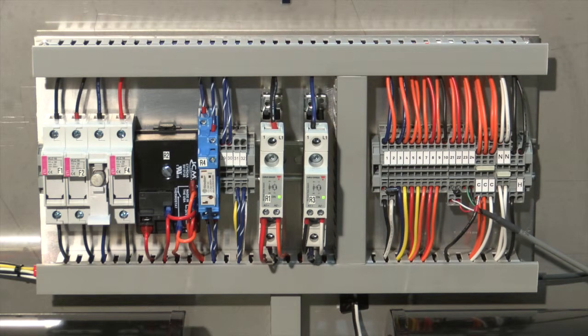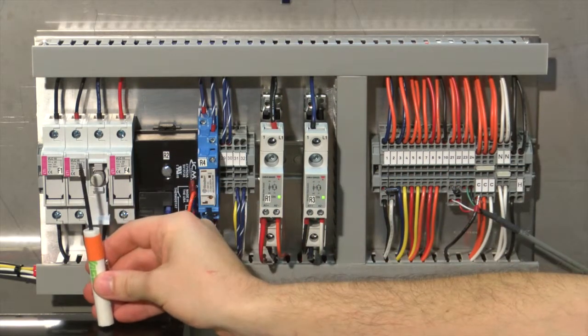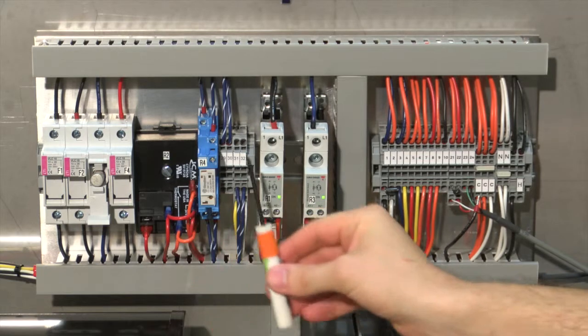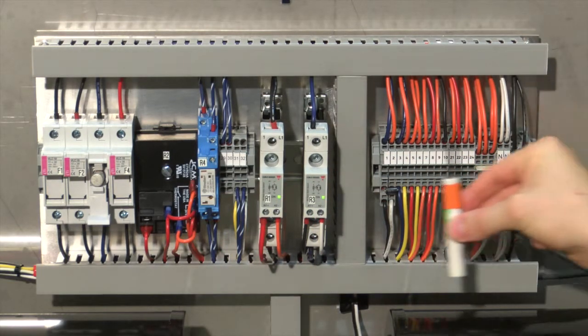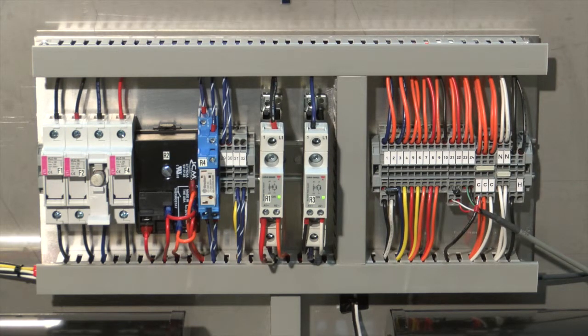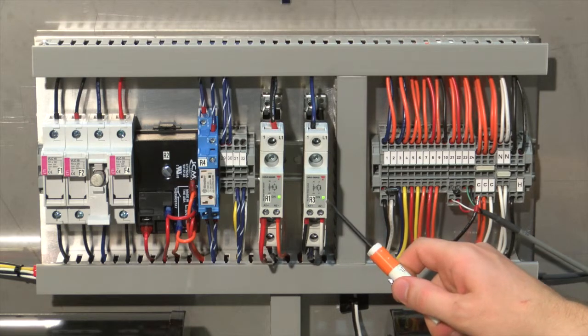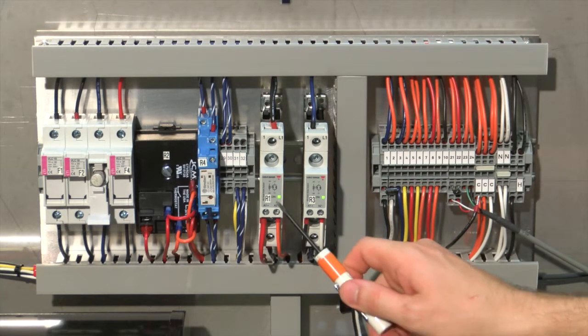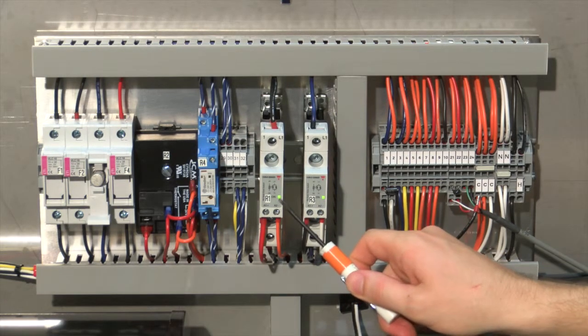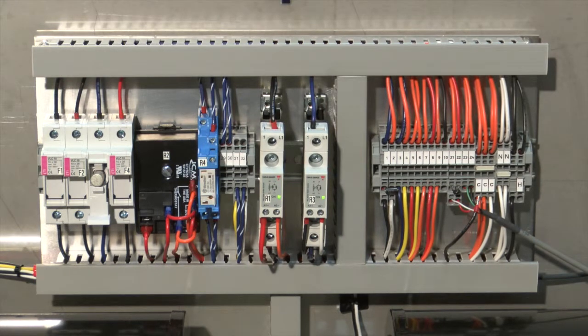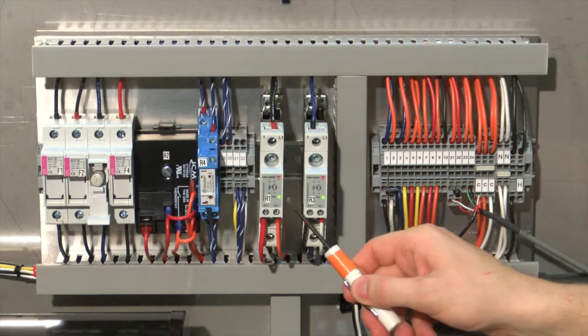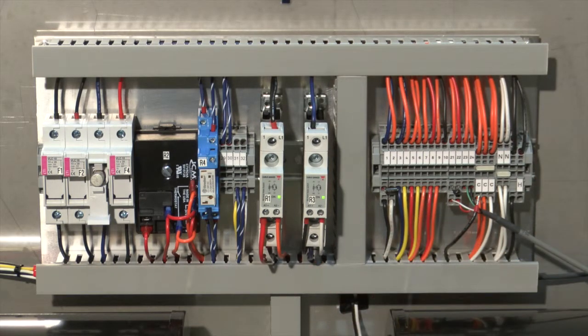A failed or damaged component will also not allow your system to operate correctly. Looking at the mist freeze interface plate, you will see the fuse block, the R2 relay, the R4, the R1, the R3, and the terminal block to connect the wiring. The transducers are controlled by the R1 and R3 solid-state relay. When the transducers are operating, both these relays should be lit green. If your transducers are not operating, also check these relays to see if they are lit. If one of these is not lit, you can follow your wiring diagram or contact Humidifirst to investigate why.